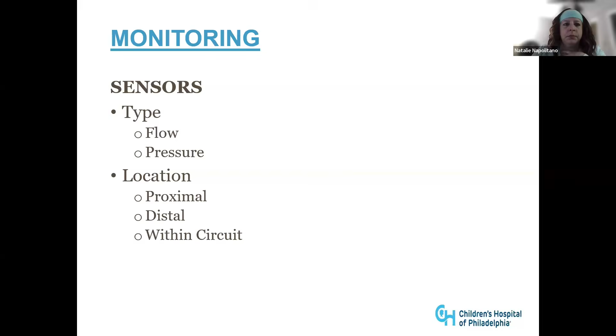But the downside to having these flow sensors within your circuit is it's a proprietary circuit. That's the only circuit that you can use on that device. And if you're in an area where you have limitations on your products getting to you, then you have no choice but to purchase, which can be very expensive, that circuit only. You can't go to other circuits because all of your sensors are within the circuit. So that is a challenge.